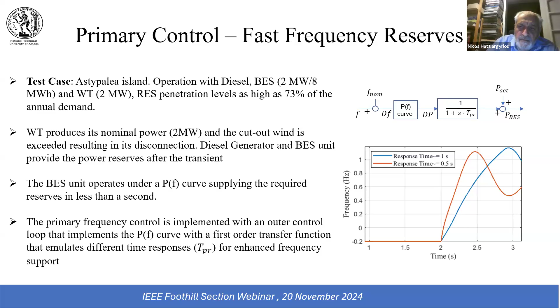Then by looking at this transient, you see that even with fast response of 0.5 seconds by the battery, the frequency decays to less than 49 Hertz, which means that under frequency load shedding relays could operate in this case. And also, if you look at the rate of change of frequency in the lower diagram, at the beginning of the transient, again, you can see that the rate of change can exceed the threshold of the loss of main relay generators. So this would lead to a further disconnection of generation units.